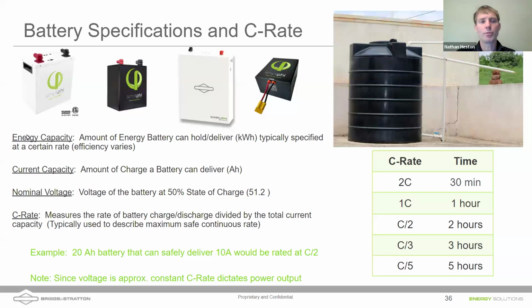Again, we mentioned before energy capacity. That's how much energy a battery can hold, typically specified in kilowatt hours. That's actually specified at a certain temperature as well. Under low temperatures, you'll get less energy out of batteries. You get the most energy out of your battery around 40 Celsius. The kilowatt hour rating of a battery is typically done at 25 Celsius, a full discharge cycle at ambient temperature. That tells you how much energy your battery will hold and deliver.